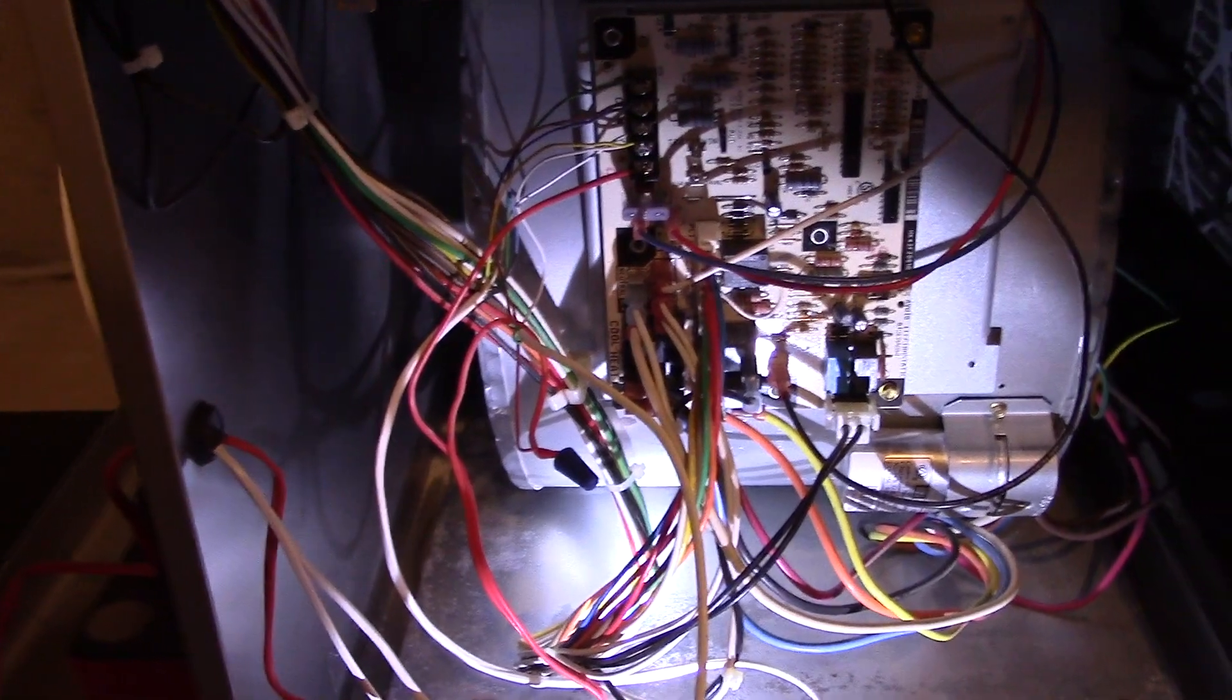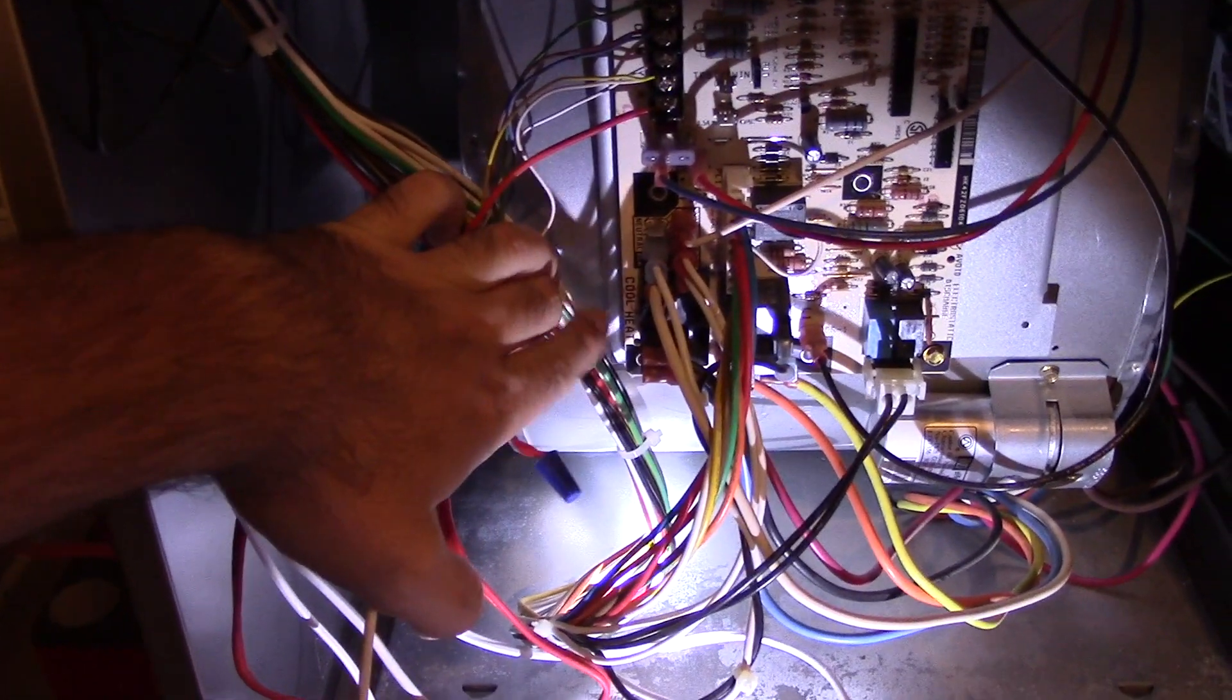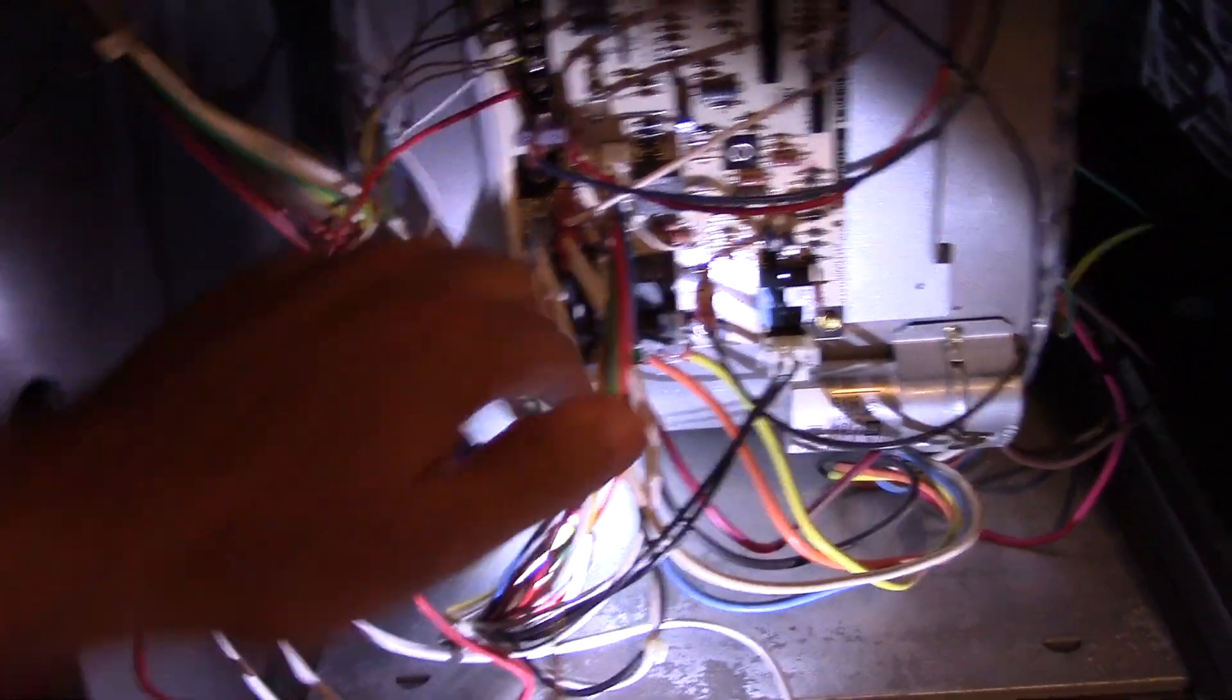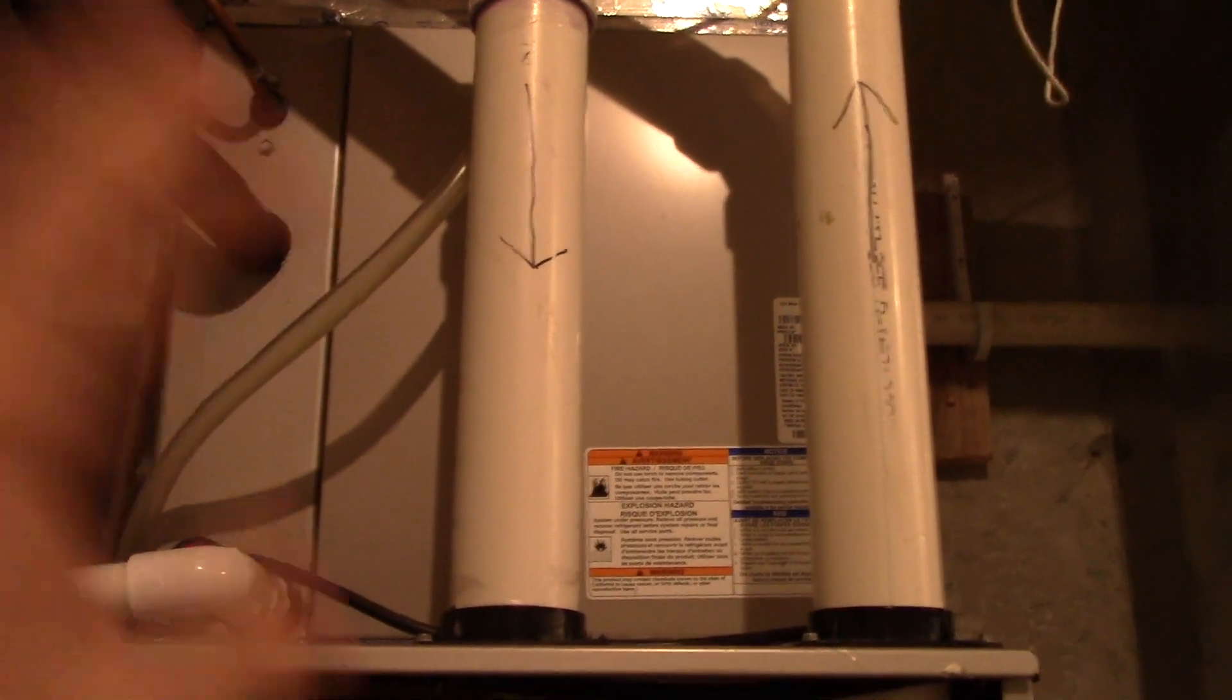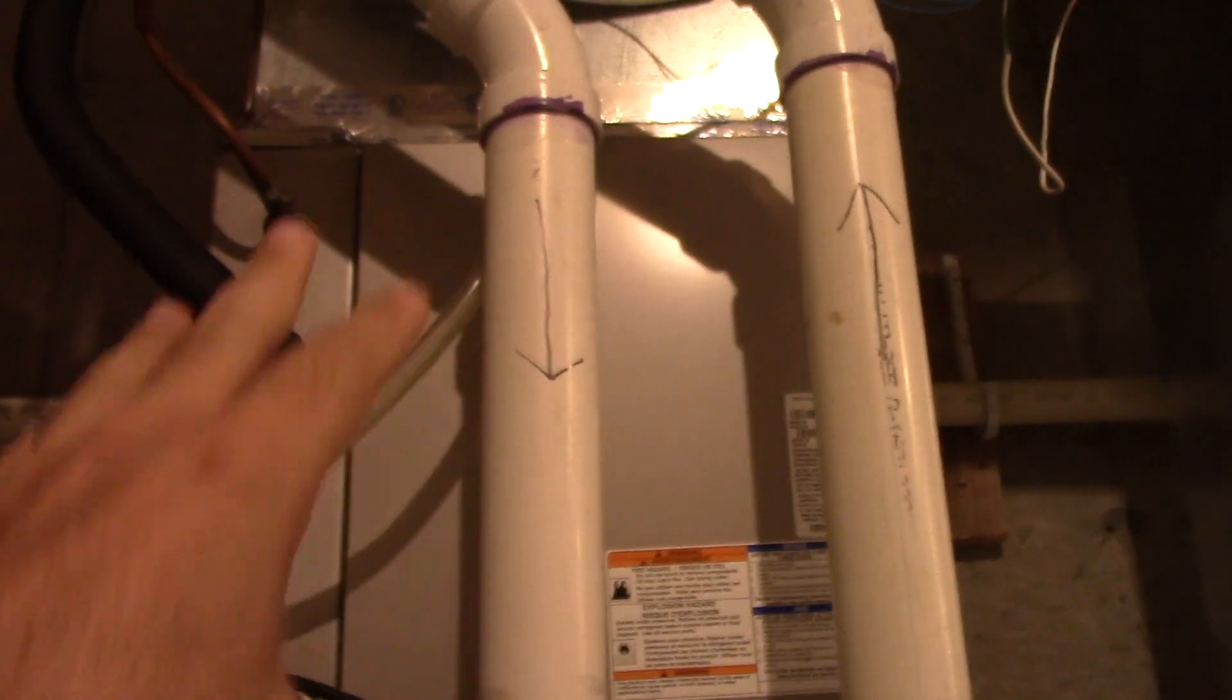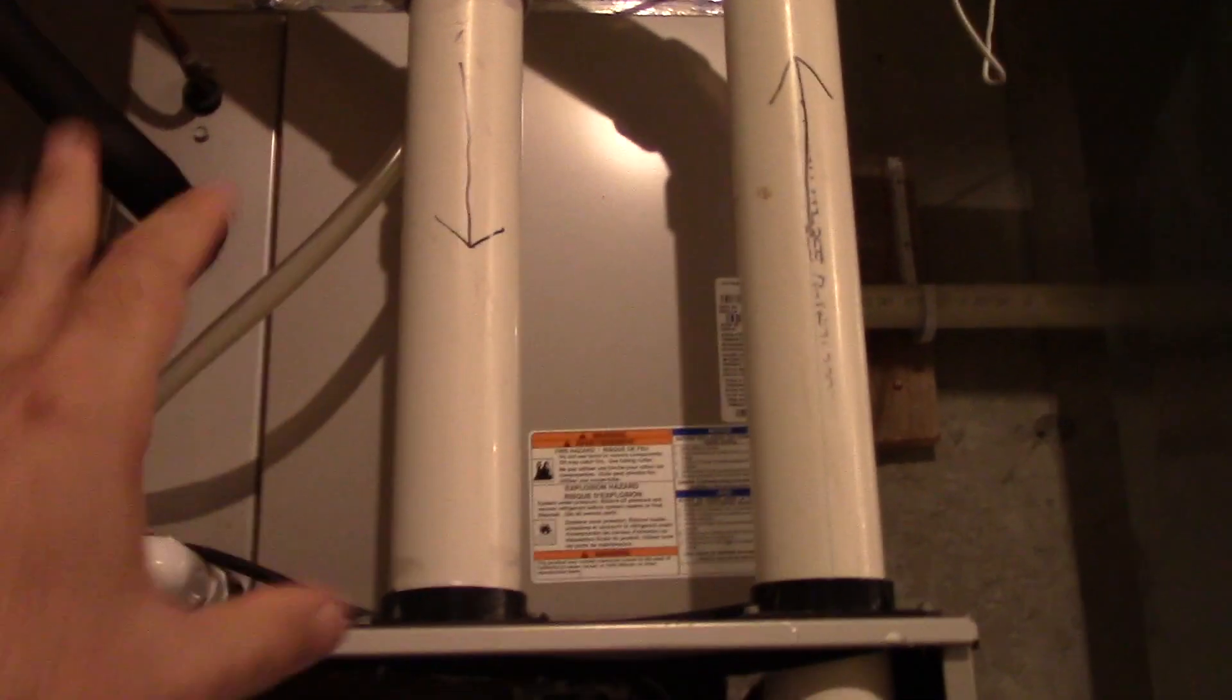If you want to change your speed, there's a couple things I want to mention first. Your air conditioning speed is set to the highest speed. I do not recommend lowering your air conditioning speed, and I'll tell you why. Your evaporator coil, which is right inside there, that's not only dependent on refrigerant pressures, but it's also dependent on good airflow for it to work properly. That's the part of the air conditioning circuit that absorbs the heat in the air and cools it down.